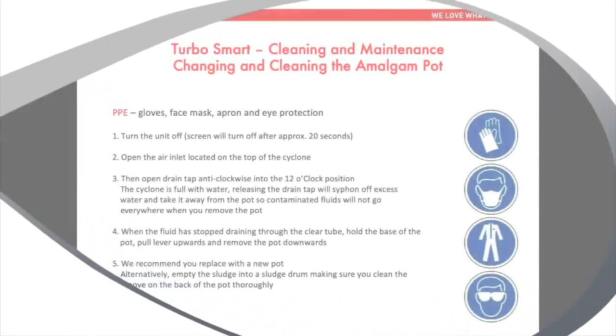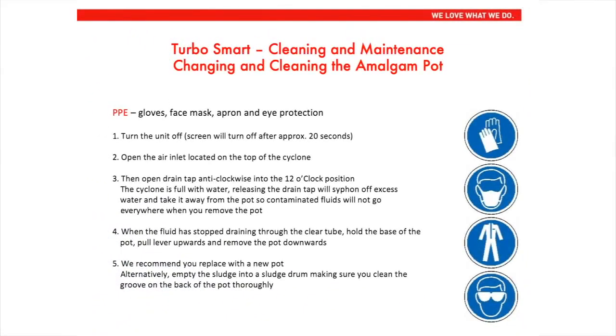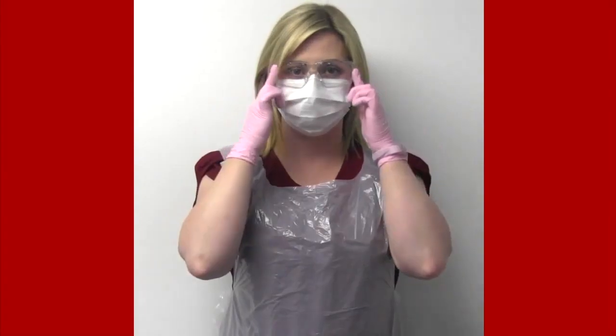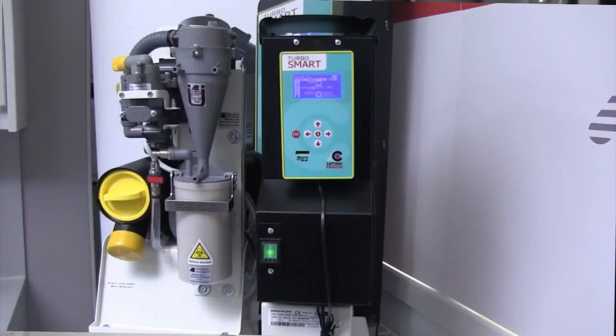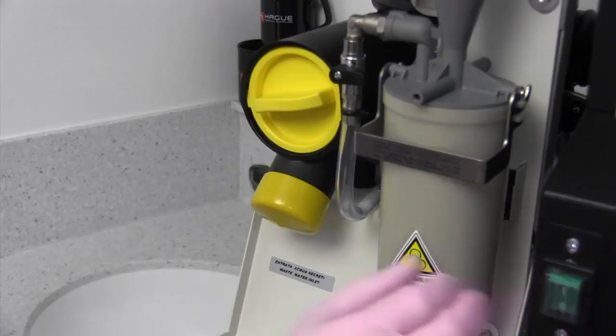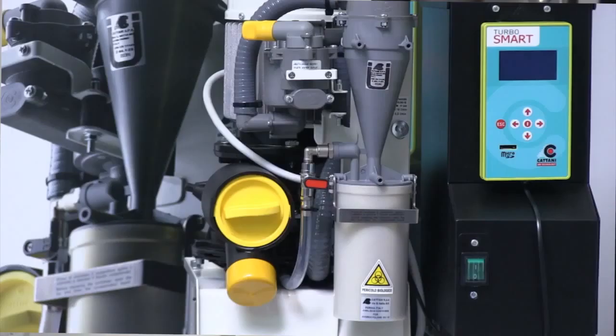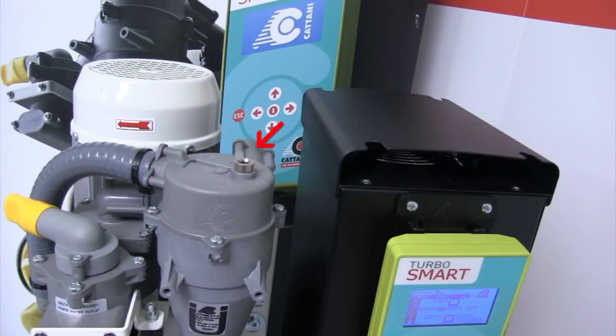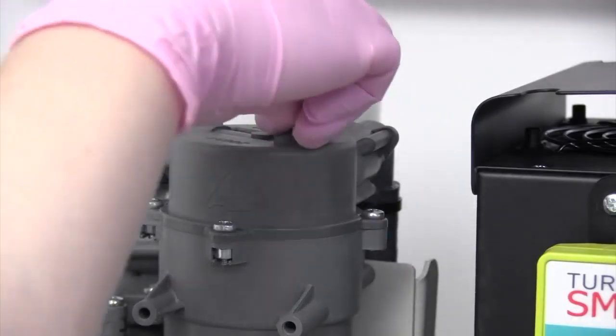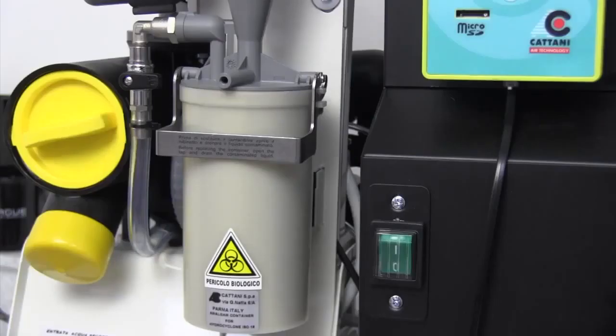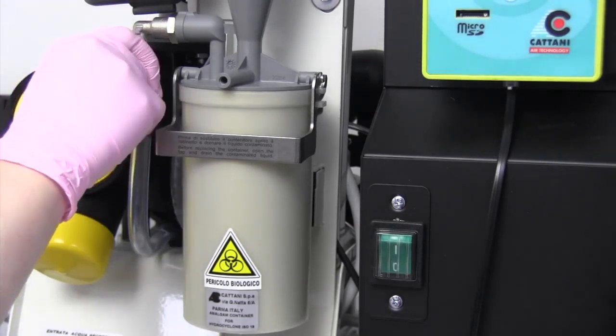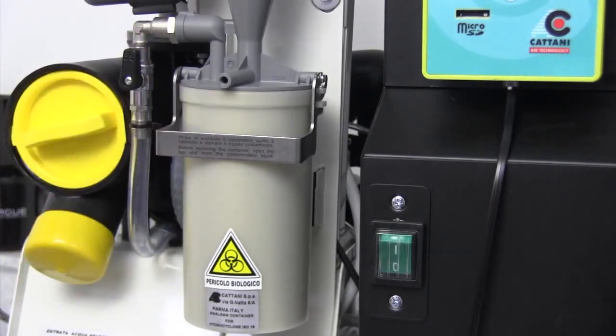TurboSmart cleaning and maintenance, changing and cleaning the amalgam pot. Again, we would recommend PPE, gloves, face mask, apron and eye protection. Firstly, turn the unit off. The screen will turn off after approximately 20 seconds. Number 2, open the air inlet located at the top of the cyclone. Number 3, open the drain tap anti-clockwise into the 12 o'clock position.